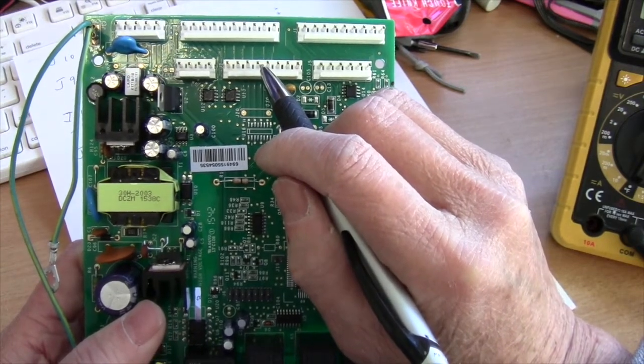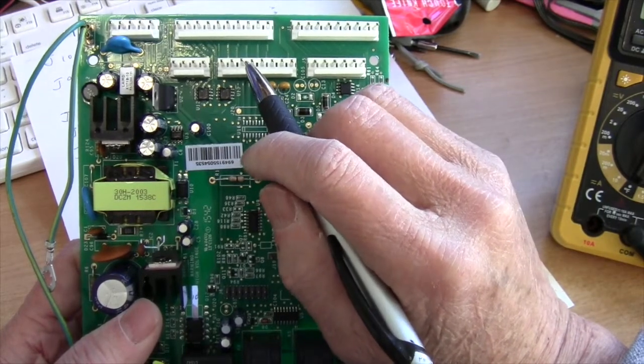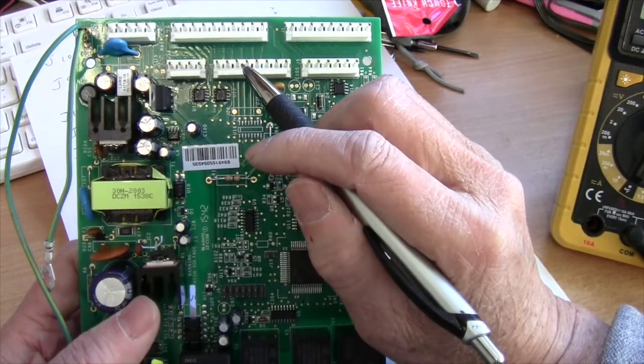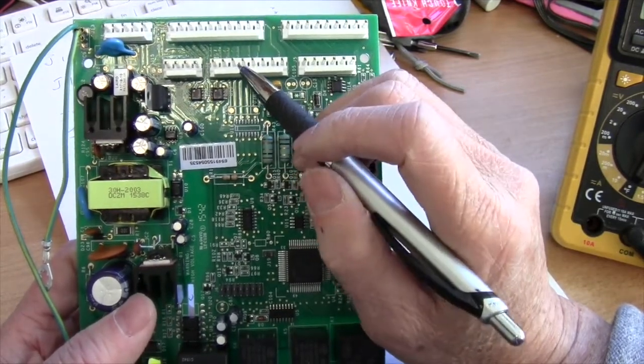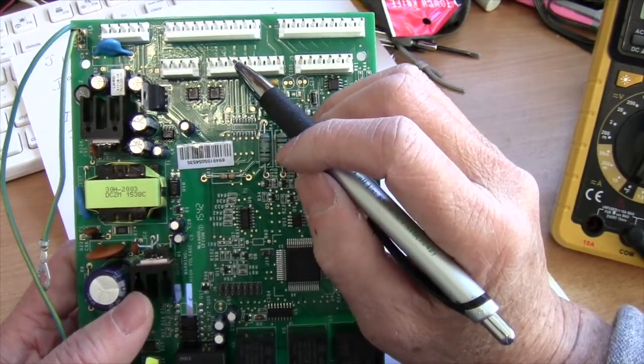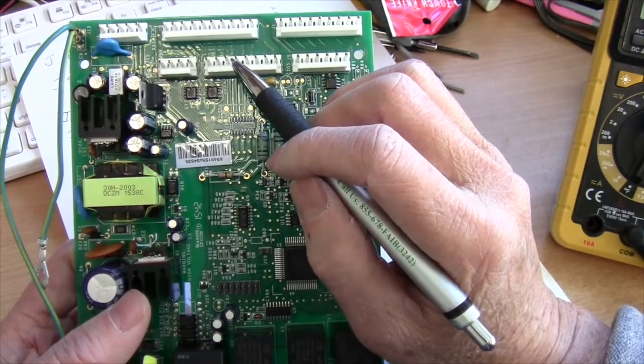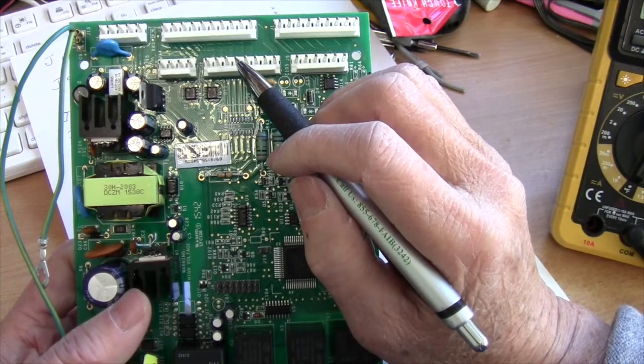That's the evaporator fan. You should get between eight to 12 volts. And sometimes you might get four to 12 volts depending on your refrigerator. I think mine just has two speed or like a variable speed. So pin three and four, eight to 12 volts.